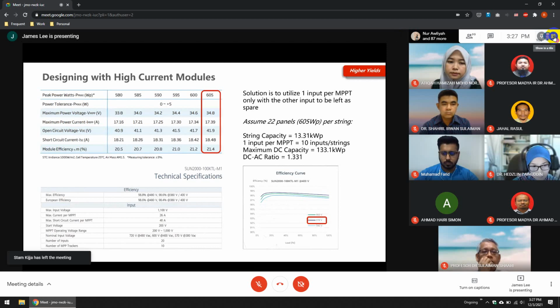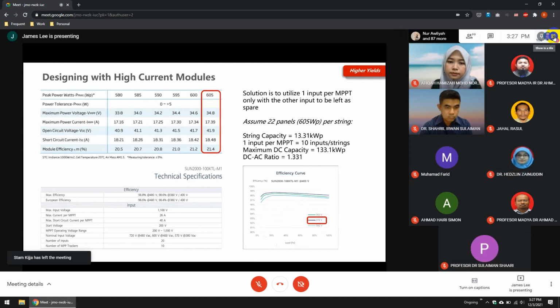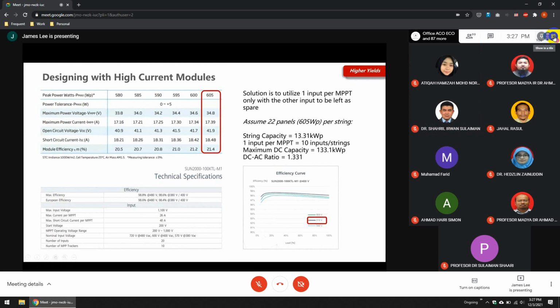A lot of times when people design, they just look at the maximum string length in terms of panels per string. But often we also need to consider, if we really want to optimize the system, the efficiency curve of the inverter. A lot of times you will see that certain inverters, especially central inverters, may not reach the maximum efficiency capability, depending on your string design as well.